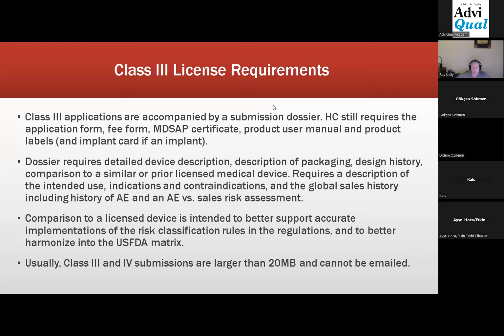And now, where Health Canada is trying to be more similar to the FDA, they're looking for a comparison to a licensed device to justify the classification. So in the past, you used to just pick which classification rule applies to my product the best, and that was it. But now Health Canada wants to know what products are licensed in the Health Canada database in that classification that are very similar to your product, to support the fact that you picked the best rule. I think that manufacturers were looking at the rules and trying to go with the weakest one. And years ago, Health Canada accepted that, and then Health Canada started challenging the rules, but it was pretty easy to defend why you chose that rule.